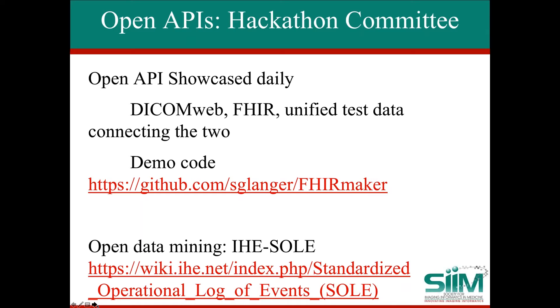Another thing that's somewhat less obvious is how you do data mining, both for research purposes or clinical workflows. Suppose you want to know the exact state of a given patient exam, or find certain types of studies for a research protocol. Every HIPAA-compliant medical device has some base set of that information, but they may not be rich enough. My colleague Brad Erickson and I worked through an IHE committee to develop IHE SOLE — Standardized Operational Log of Events — now in test implementation, where compliant vendors export system logs in a standard format to a central syslog server, making data mining for clinical workflow or research much easier.